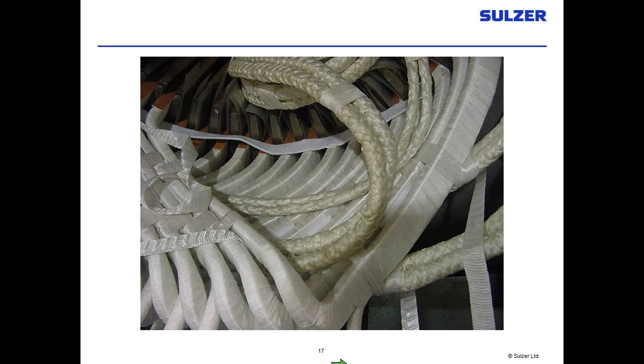Here's what the bracing looks like. You have your coils made of copper. This is actually fiberglass strands saturated in thermosetting epoxy — when it sets up, it's like a steel ring, very strong. We tie all of our coils off to that — on the bottom, to the inside — and we have tangential blocking to keep coils from moving side to side. These thermosetting tapes will shrink a little and pull your winding together, because we are trying to create a homogenous mass with the coils as much as we can. This is all done before the VPI process, which sets your coils in further. Make sure you have adequate blocking in your motor rewind.